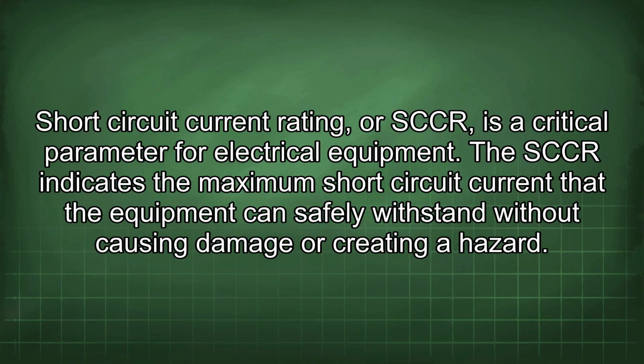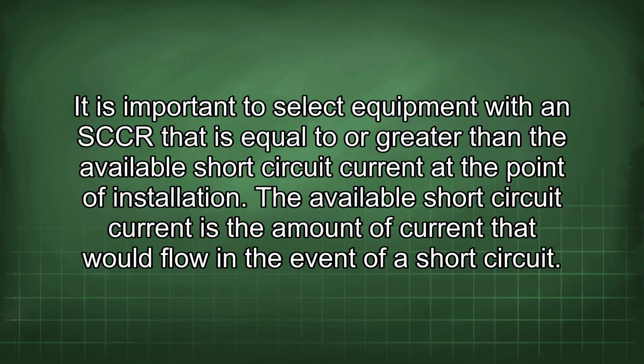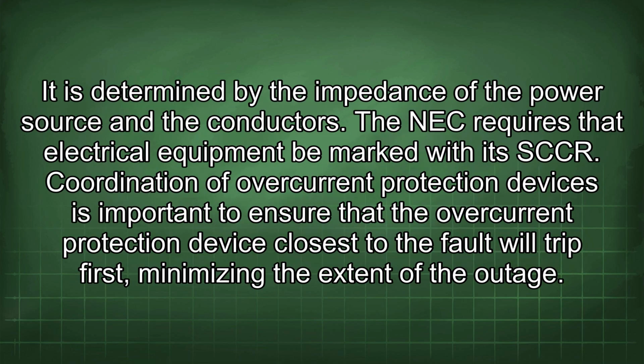Short circuit current rating, or SCCR, is a critical parameter for electrical equipment. The SCCR indicates the maximum short circuit current that the equipment can safely withstand without causing damage or creating a hazard. It is important to select equipment with an SCCR that is equal to or greater than the available short circuit current at the point of installation. The available short circuit current is the amount of current that would flow in the event of a short circuit. It is determined by the impedance of the power source and the conductors. The NEC requires that electrical equipment be marked with its SCCR.